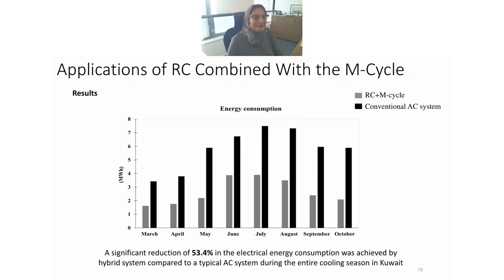What matters now is the energy consumption. A significant reduction in electrical energy consumption was achieved - 53% of electric power was reduced compared to the conventional AC system. You might ask where this electrical power comes from for the hybrid RC-M-cycle system. It's really the redundant power from pumps and fans, because you have fans driving the air in the duct, and the water cycle needs a pump for the water conversion.